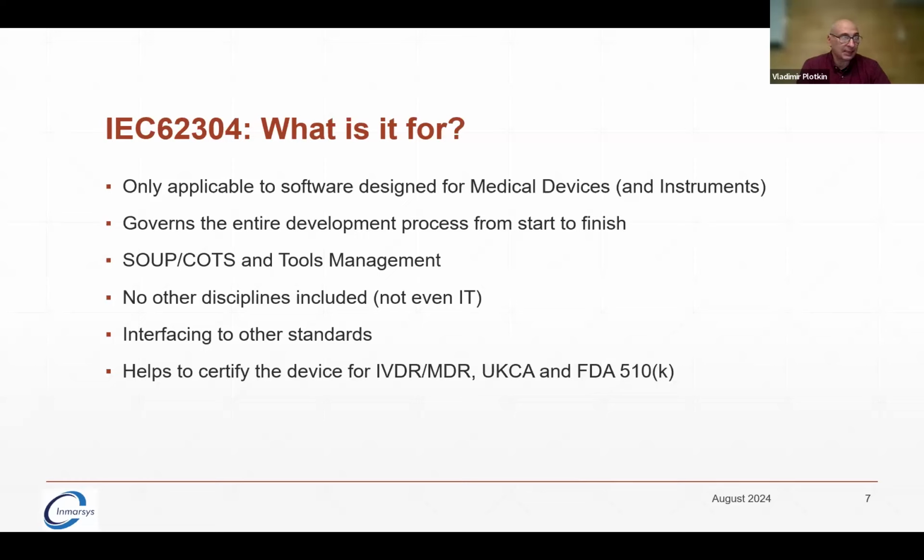So that's basically it. The purpose of it is to accelerate the certification, the submission for the device, and placement on the market. Here on the presentation I'm talking about 510(k), but not necessarily. It can be De Novo as well. It all depends on how you position your device, whether there is any predicate to the device or not.